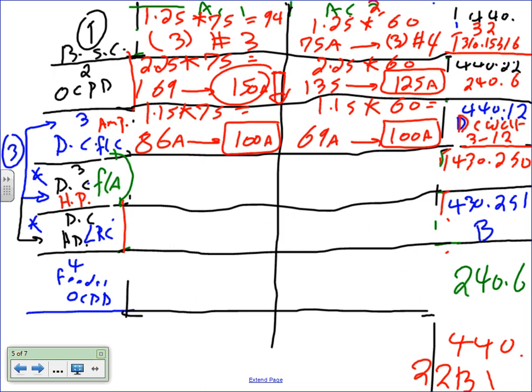Take the first one. What's the full load amp of this one? It was 75. If you take it to table 250, what does it translate to in terms of horsepower? 60. It translates to 60 horsepower. Same thing for the other one, 60 amp. These are amps. If you take it to 430.250 under 480, it translates into 50 horsepower. So that's how you translate, because I don't know what the horsepower rating for this disconnect is. I don't have a horsepower for these equipments. So based on the full load amp, you can find the horsepower.